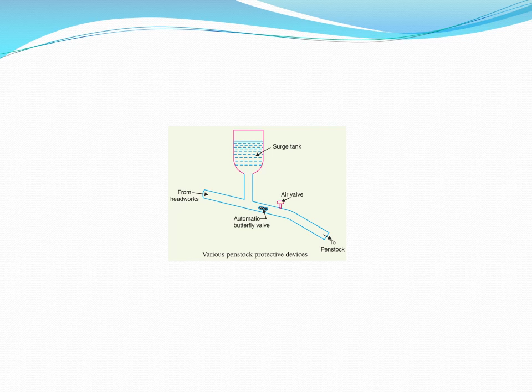The fifth part of hydroelectric plants is penstocks. Penstocks are open and closed conduits which carry water to the turbine. They are generally made of reinforced concrete or steel. Concrete penstocks are suitable for low heads, meaning below 30 meters, as greater pressure causes rapid deterioration of the concrete. The steel penstock can be designed for any head. The thickness of the penstock increases with the head or working pressure.